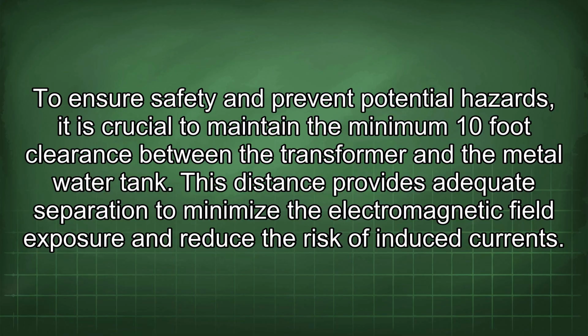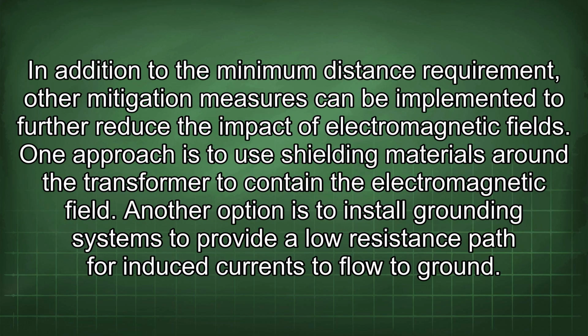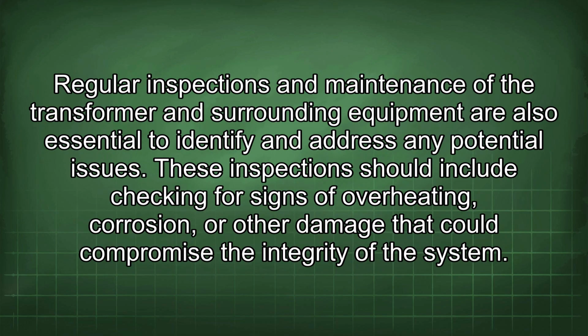induced currents. In addition to the minimum distance requirement, other mitigation measures can be implemented to further reduce the impact of electromagnetic fields. One approach is to use shielding materials around the transformer to contain the electromagnetic field. Another option is to install grounding systems to provide a low-resistance path for induced currents to flow to ground. Regular inspections and maintenance of the transformer and surrounding equipment are also essential to identify and address any potential issues.